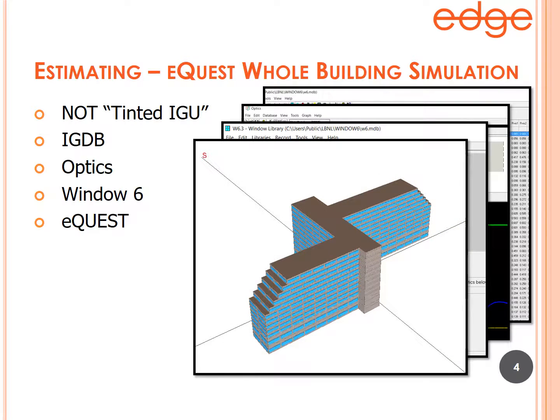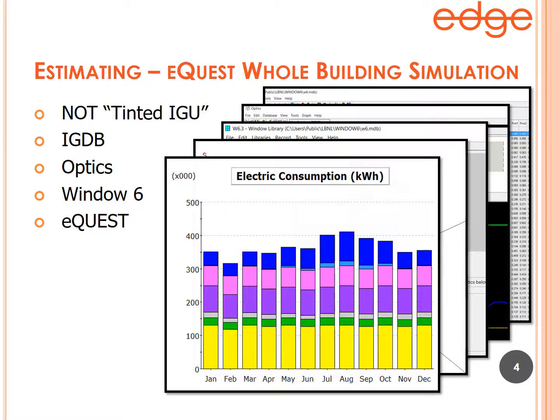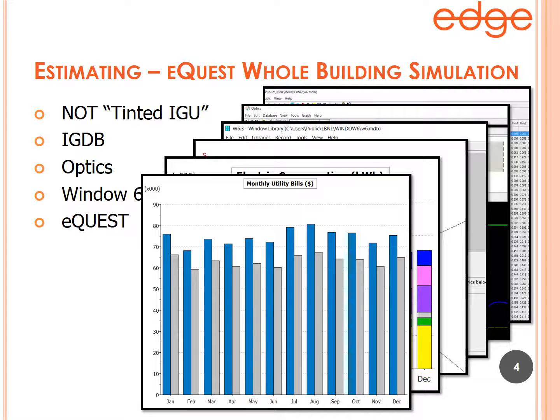We then take that actual window performance and bring it into our eQUEST energy simulation. This is an example of a hotel built in eQUEST to provide a building shell that significantly resembled the actual hotel. The blue windows you see here have been built using the actual glass type, both before and after the application of window film. The results from eQUEST include consumption, demand, and gas consumption broken up by energy system, as well as monthly utility costs for both gas and electric.